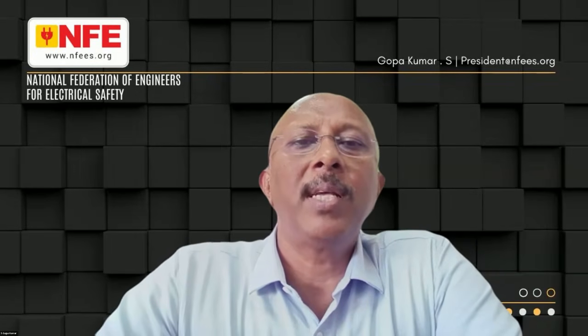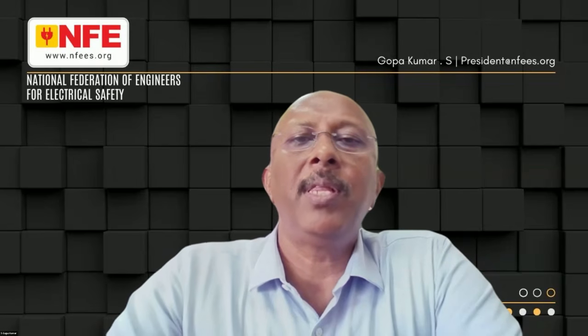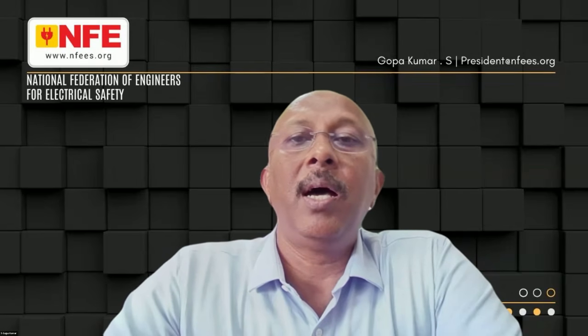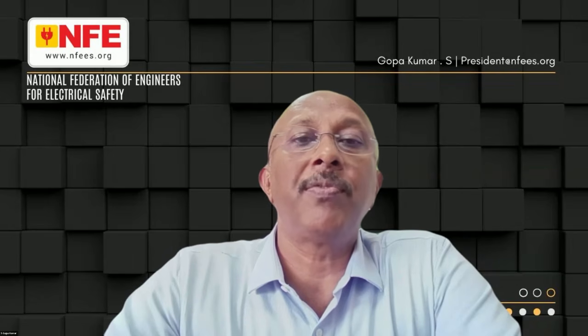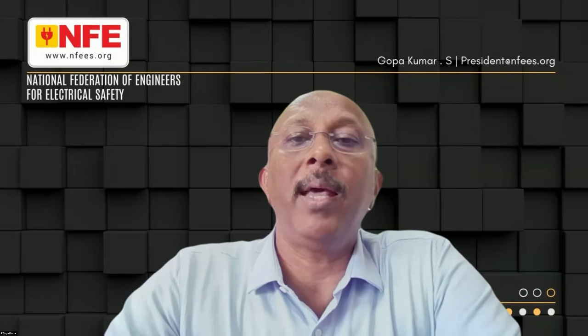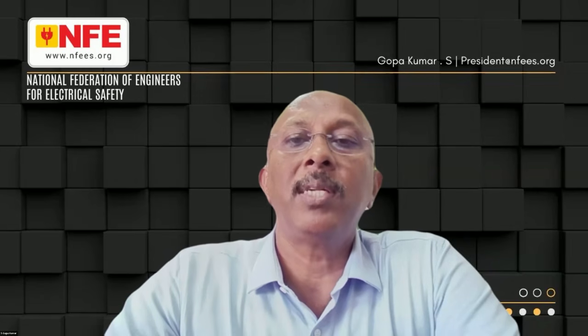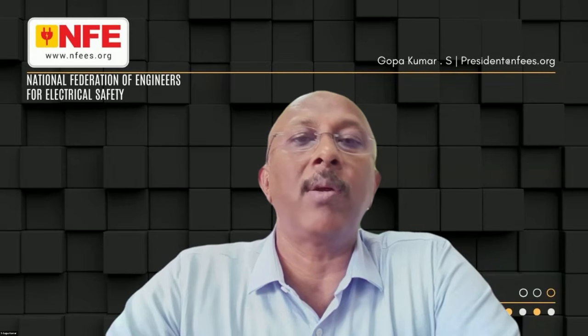So Mr. Sunil Kumar is asking, as per IEC and NEC 2023, it is specified equipotential bonding with the one earth electrode. Suppose if the sole earth electrode got damaged, how the reliability will be ensured? Also, if the soil resistance is more, how the touch potential will be limited with one earth electrode?